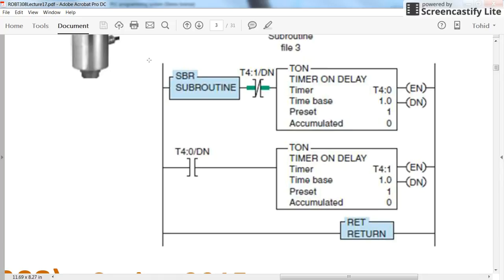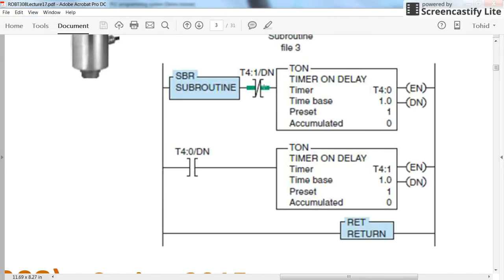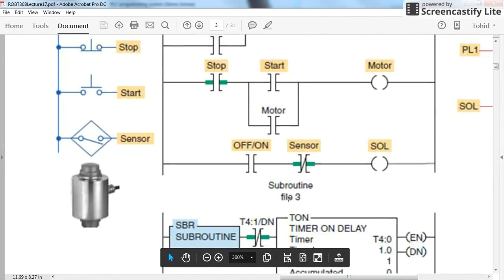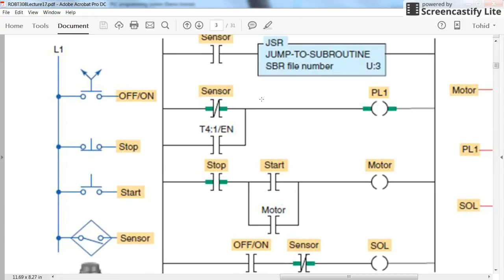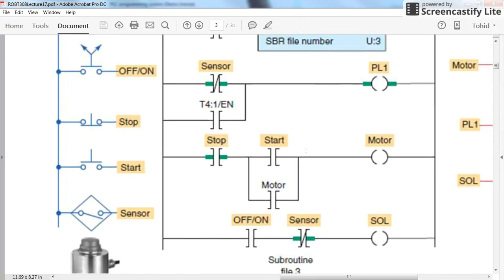So whenever it is called, then here we will have two on-delay timers connected to each other in this way. The done bit of each one is acting as the enable bit of the other one, providing input. And then the output of the timer is used here in the original program. The enable bit of timer one or the done bit of timer zero is used in parallel with the sensor contact in order to turn on or off the pilot lamp number one.